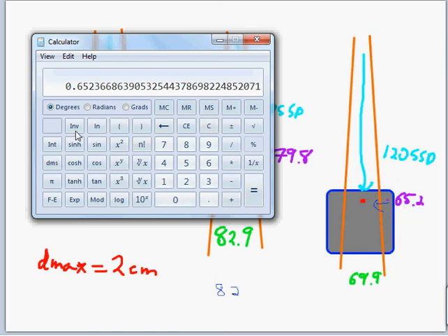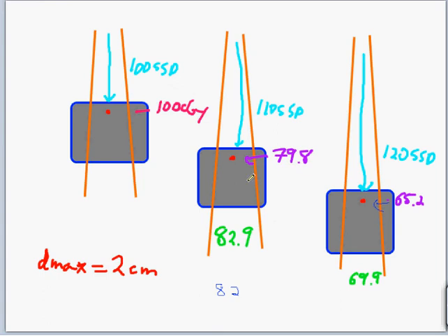That's just what we measured. So that looks good. So we'd say we can use that if, say, we're going to go to 5 centimeters. We would use what we call the VSD, virtual SSD, of 82 centimeters to figure out the distance factor. And the formula for that is like this.